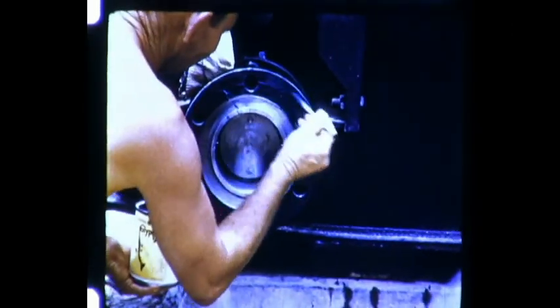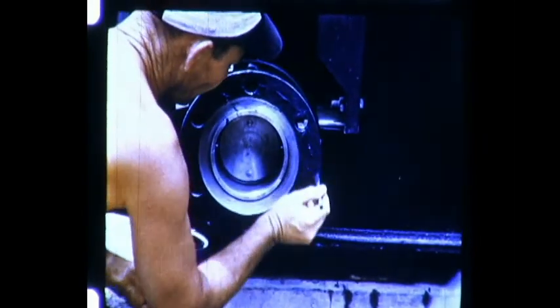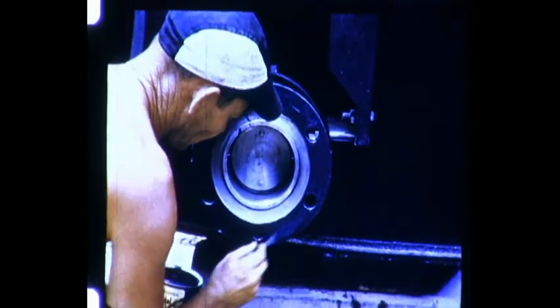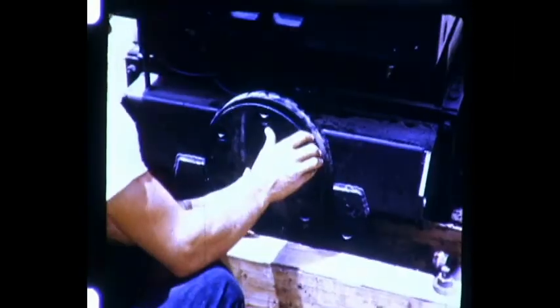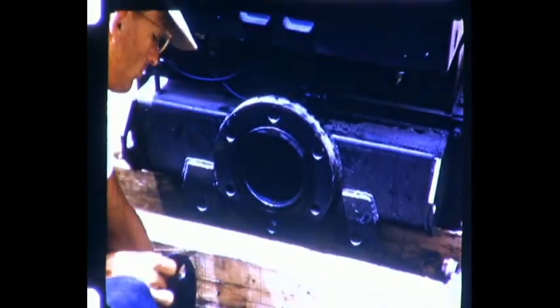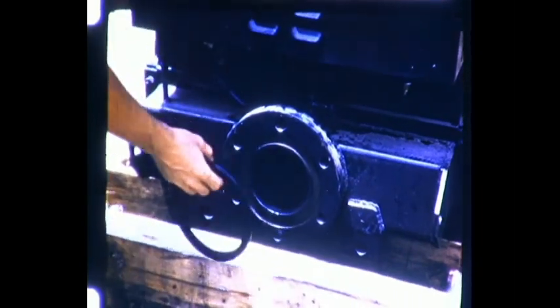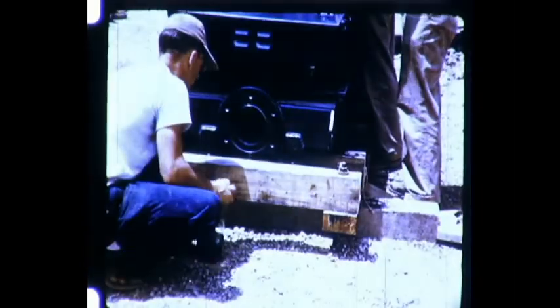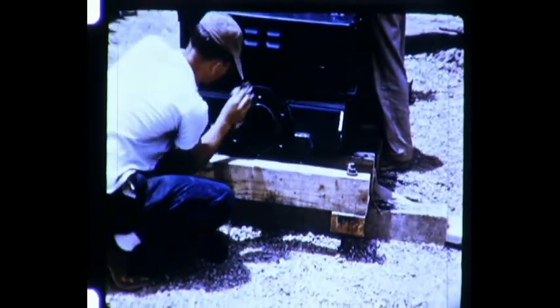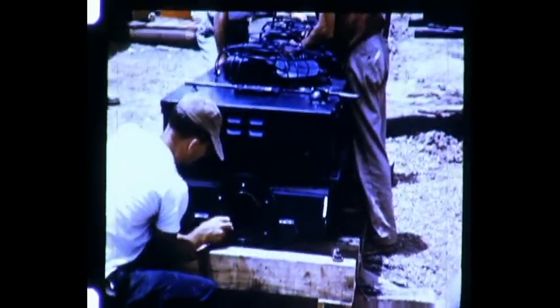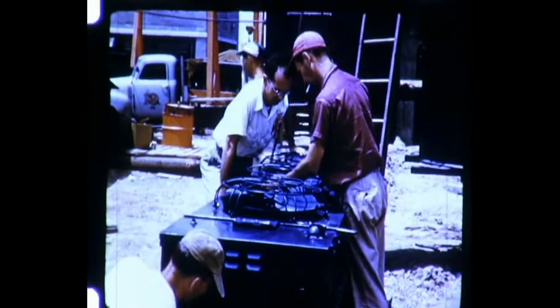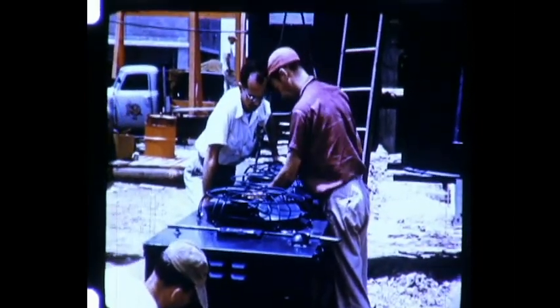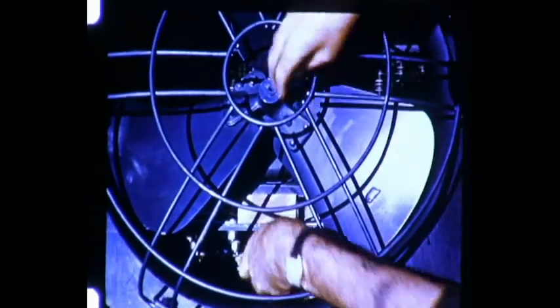The lower shutoff valve is shipped on the transformer, and here again the gasket surfaces are cleaned with denatured alcohol and the flange retouched if necessary. The bottom of the cooler will be secured to the lower shutoff valve by a connecting elbow. All gaskets used for shipment are made of nitrile rubber and thus have the advantage of being reusable for final assembly. Any blocking to be removed after shipment is marked by a red X. This block prevents damage to the cooler fan mounts during transit.